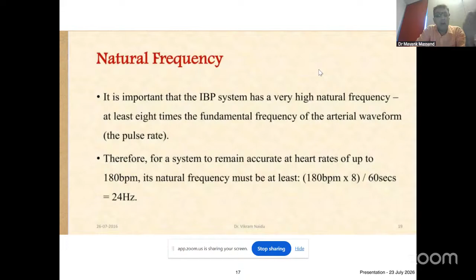Now, what things can actually increase the natural frequency? By reducing the length of the cannula or tubing, we are coming up with small tubing sets. We are coming up with naturally small cannulas to cannulate with the advent of ultrasonography. We can reduce the compliance of the cannula by providing stiff tubings or diaphragm. Reducing the density, we always use normal saline. We are not using dextrose. Increasing the diameter of the cannula or tubing, we should have a broad diameter cannula, and commercially available systems have a frequency of 200 hertz.